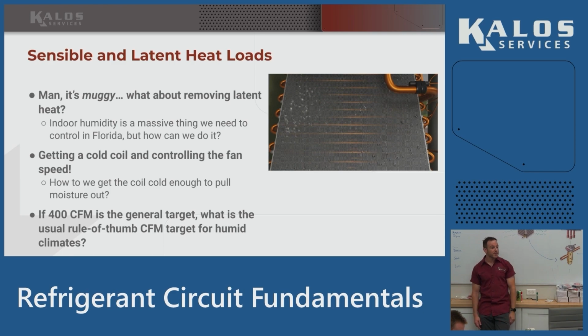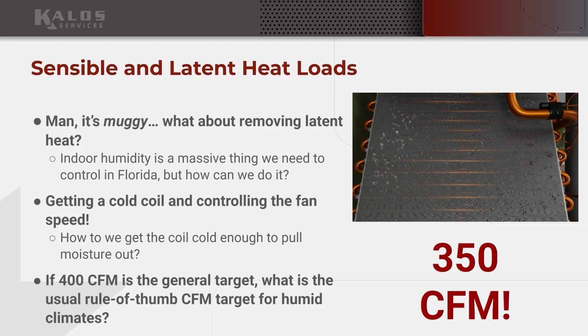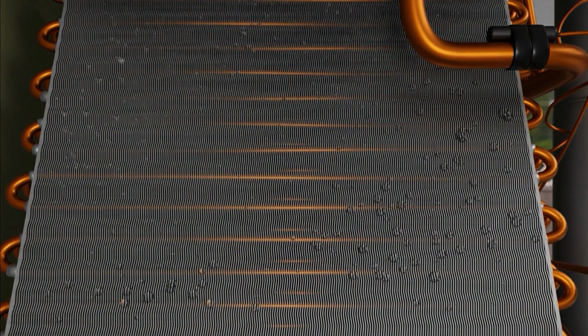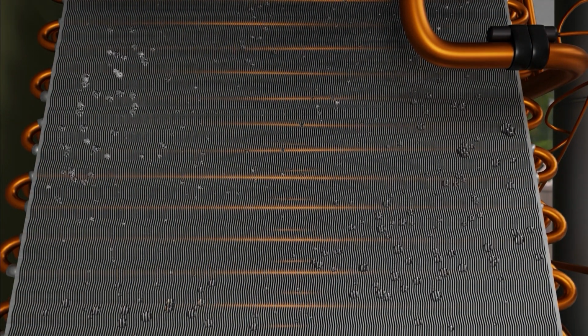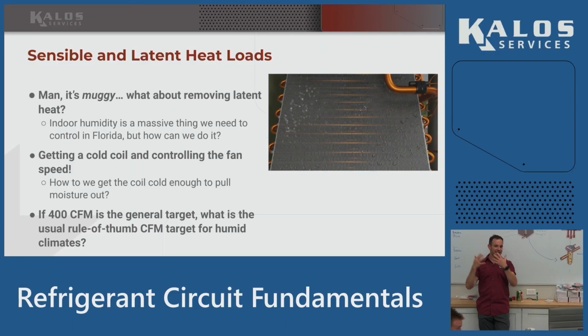Is it the humidity? Exactly. So we talked a little bit earlier, we got sidetracked talking about sensible and latent heat loads. I have water in the air. Some of the heat that my refrigerant is absorbing is going into taking latent heat from the water in the air to condense it. So I won't see as much of a sensible temperature difference in the air if I have high humidity. That's why when I'm calculating a target temp split, I'm looking at the humidity in the air. If I have high humidity, I'm not going to hit a perfect 20-degree temp split, because some of the heat that I'm absorbing is actually condensing the water into my coil. So humidity does play a huge factor.